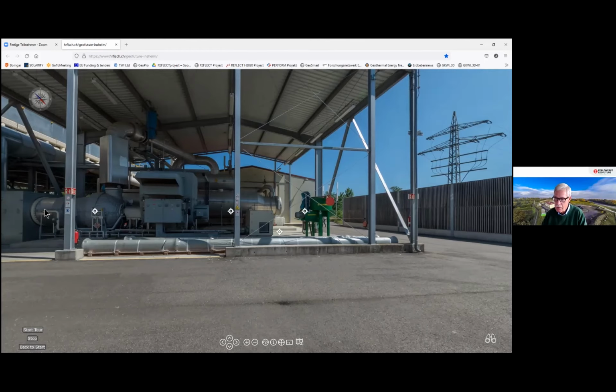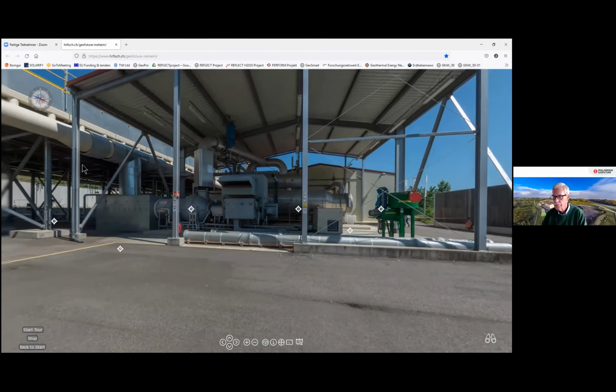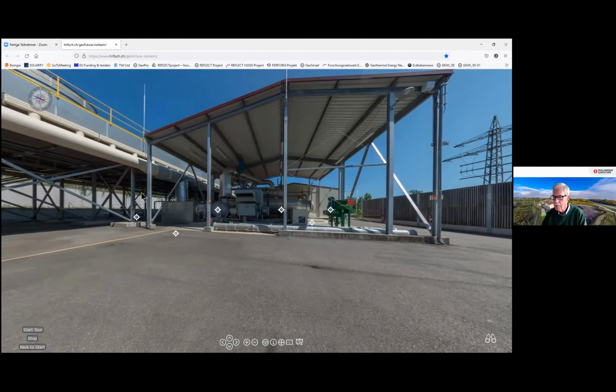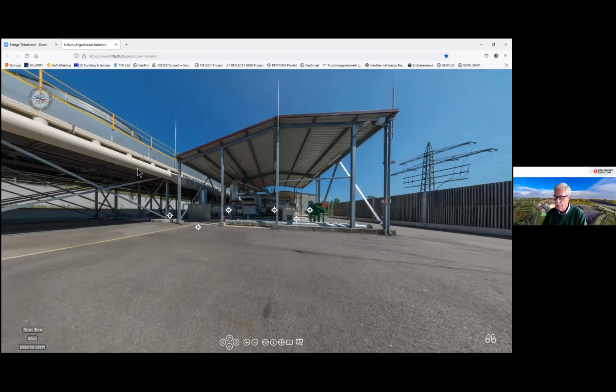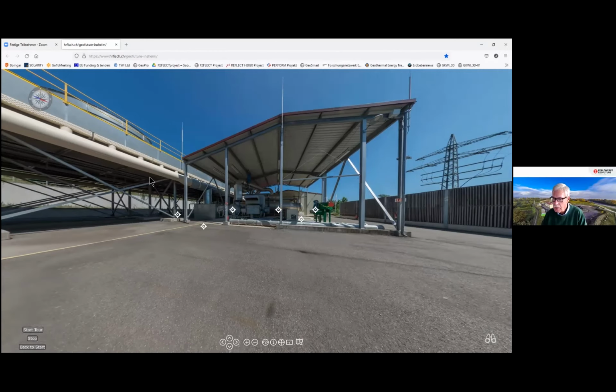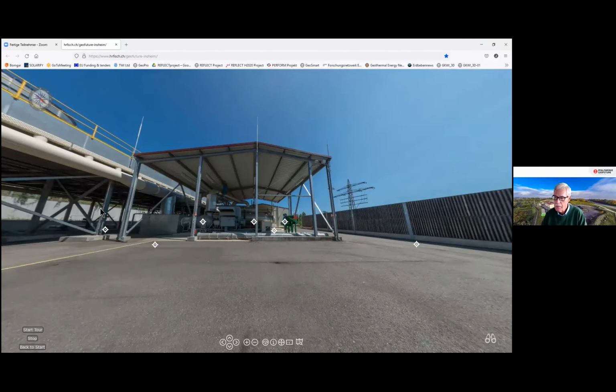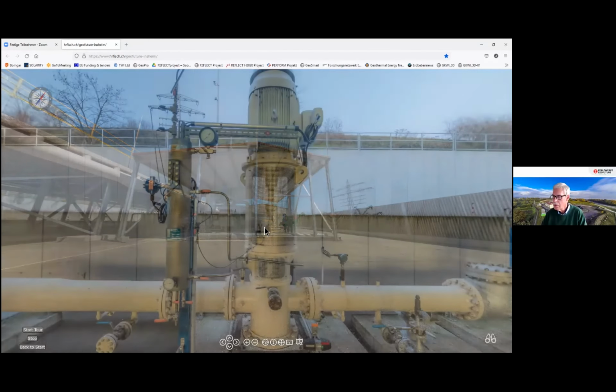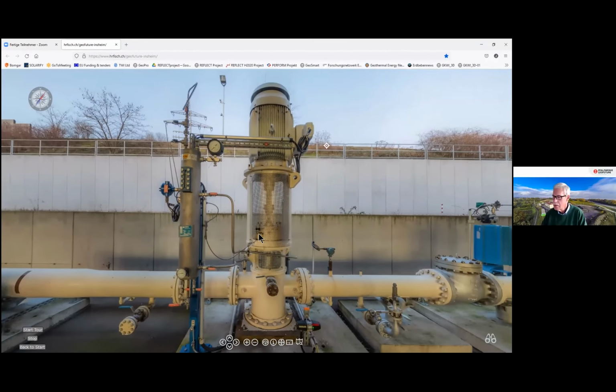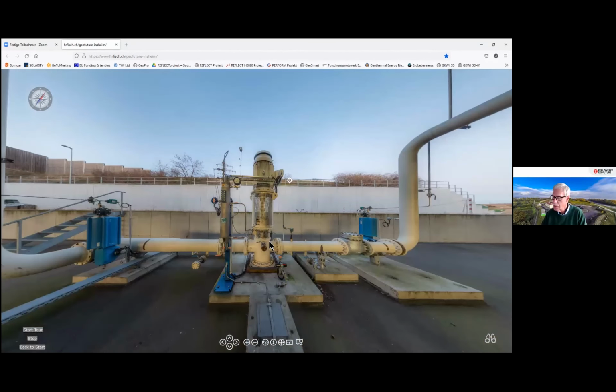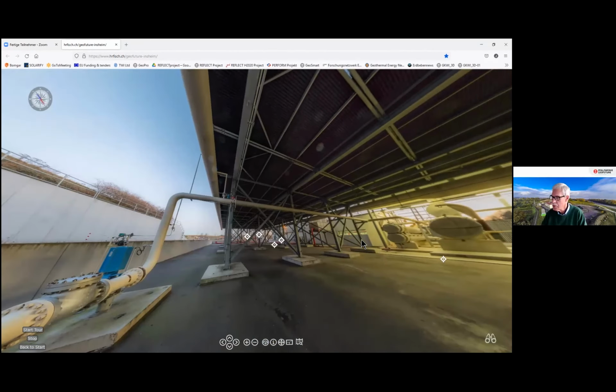and then expanding out of the turbine in a horizontal way to the left side, and from there flowing through this large horizontal distribution pipe, and then streaming through this large condenser, which is more or less working like a cooler in your car, where we have these large fans on top, and we are just having the air streaming from bottom to the top, and by this cooling down the isopentane, and when it cools down, it will condense again. And on the other side, which we'll later see, we have a so-called isopentane pump, sorry, it's not the brine pump. And this isopentane, when it's already a fluid, will then be pumped back into our heat exchangers.